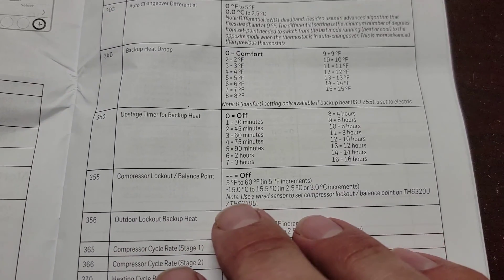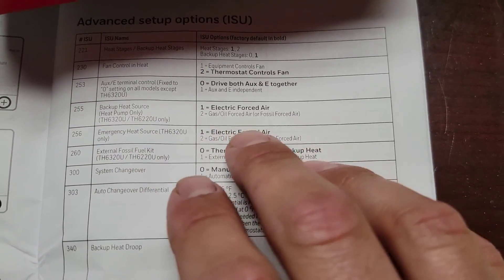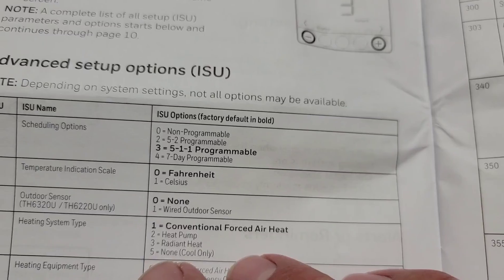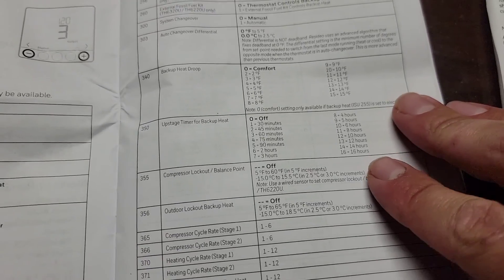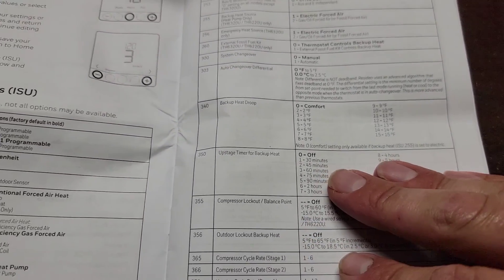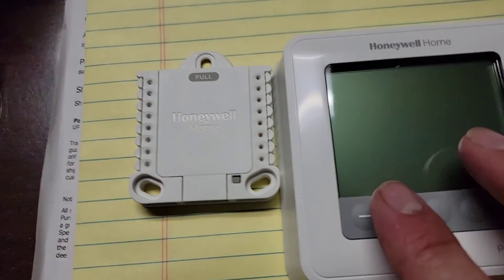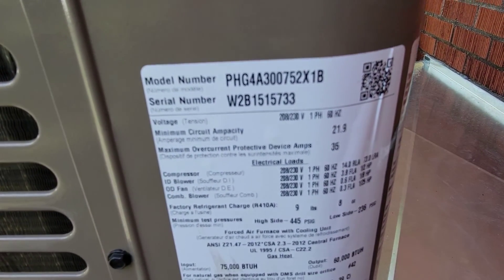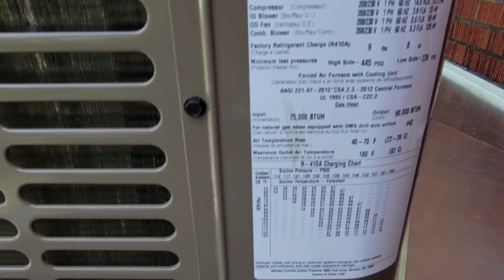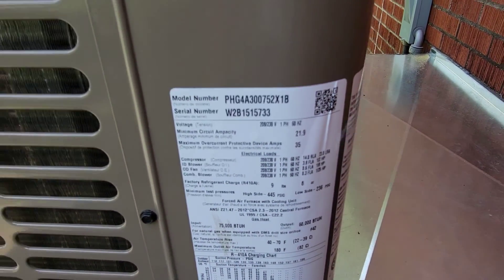If you've set the temperature correctly, set the backup heat source correctly, and set up your wired outdoor sensor correctly, you should be in good shape and the unit should work. If you want to test it, turn it into emergency heat — go to your thermostat, push the mode button until it says emergency heat, and you're good to go. This unit is a PHG4A30075 — it's a two and a half ton because it's 30,000 BTUs cooling, and 75,000 BTU heating.